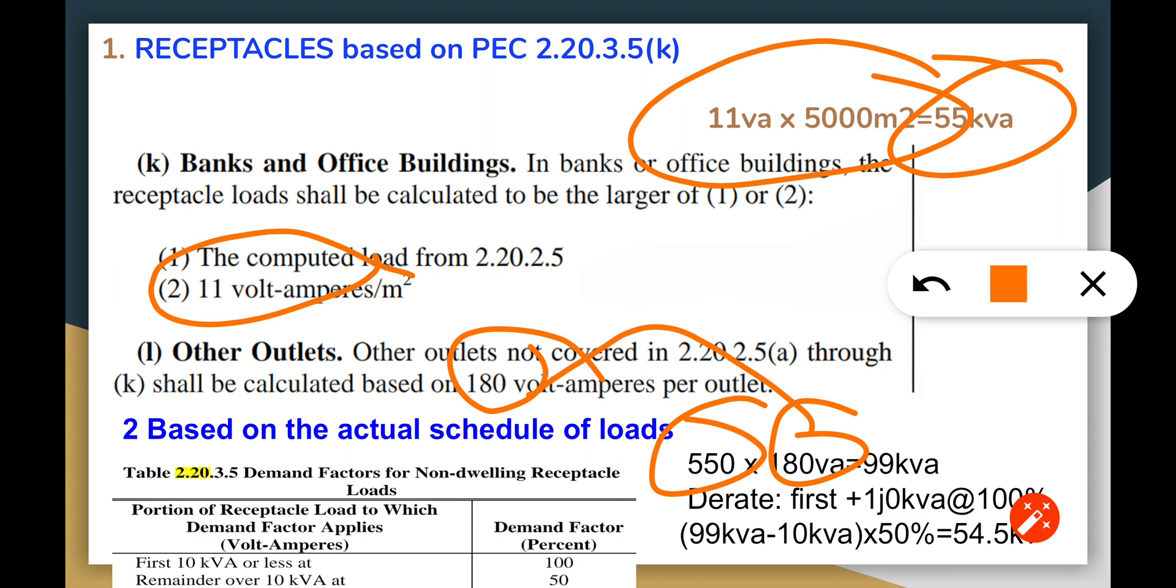According to the rules, if we have more than 10 kVA we have to derate based on this table. So we have the first 10 kVA at 100 percent, and 99 minus 10 kVA cut it to 50 percent, and we shall have 54.5 kVA. But we have the largest at 55 kVA, so this is where we're going to use the 55 kVA.